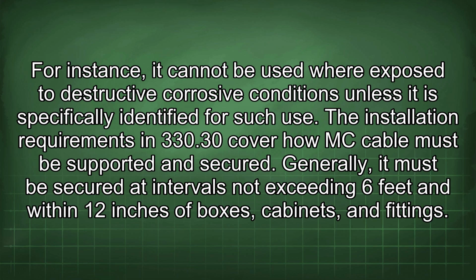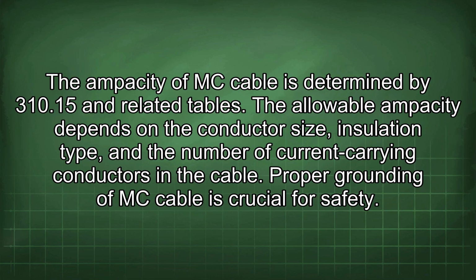The installation requirements in 330.30 cover how MC cable must be supported and secured. Generally, it must be secured at intervals not exceeding 6 feet and within 12 inches of boxes, cabinets, and fittings. The ampacity of MC cable is determined by 310.15 and related tables. The allowable ampacity depends on the conductor size, insulation type, and the number of current carrying conductors in the cable.